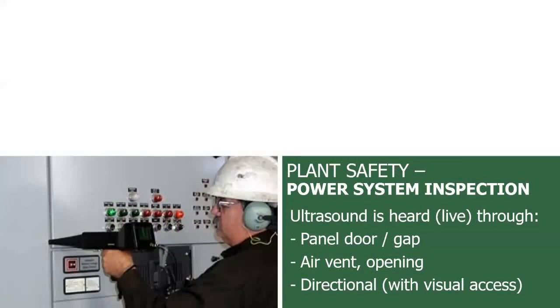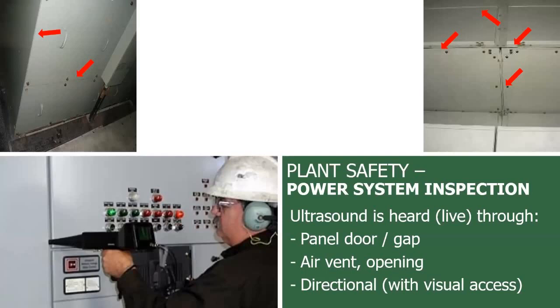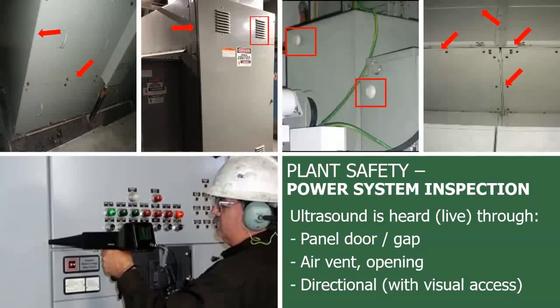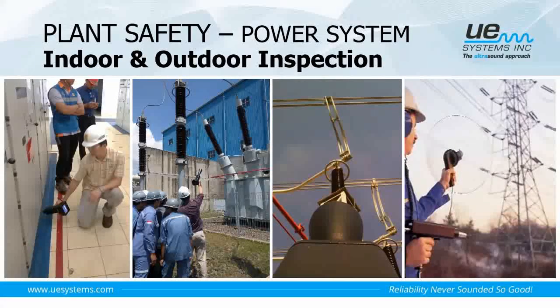Ultrasound is heard through a panel door, gap, air vent, and opening. If we have visual access, then we can assess, evaluate, or detect the symptom through a directional access. The ultrasound device is applicable for indoor application or outdoor inspection. We can apply it on an outdoor transformer, outdoor switchyard, or even overhead towers. Let's look at a short video about power system inspections.